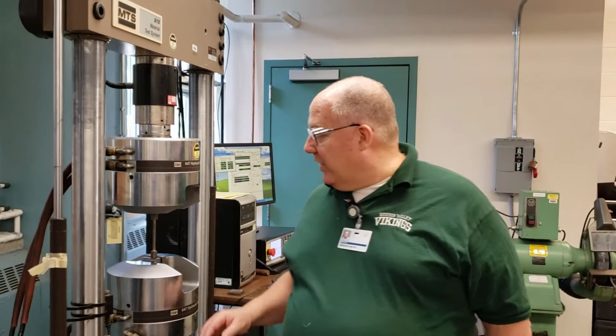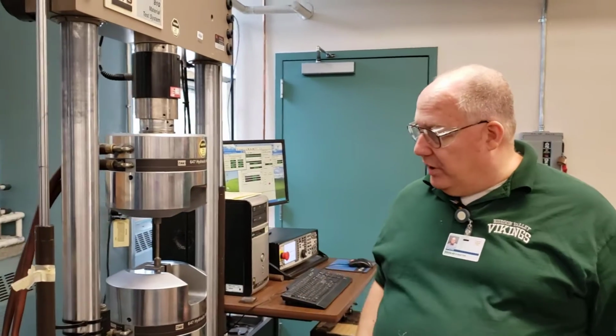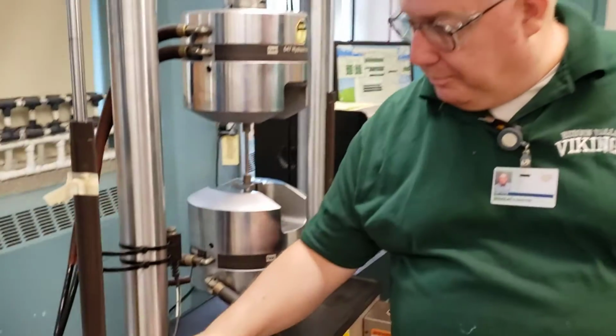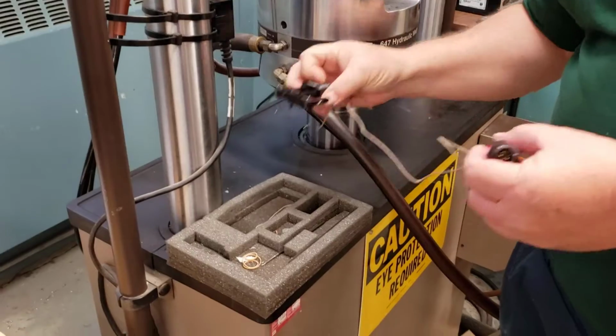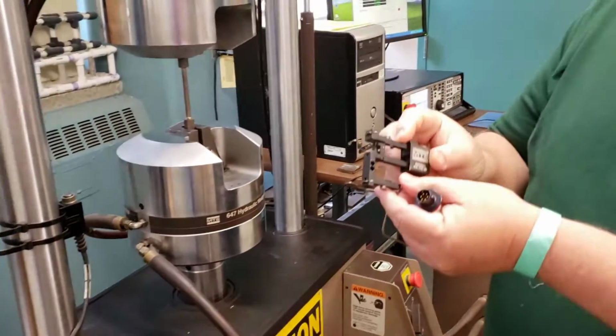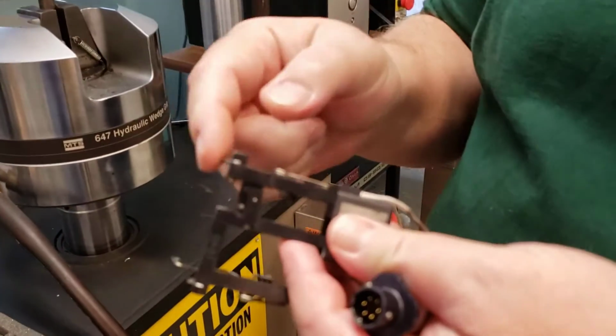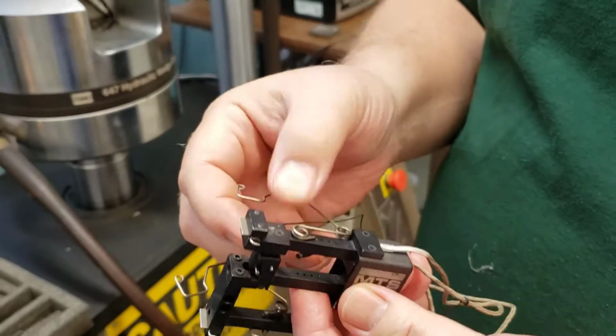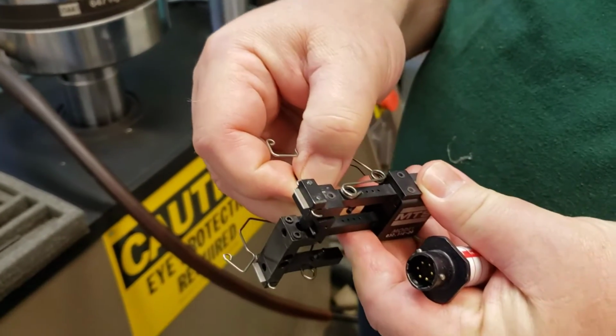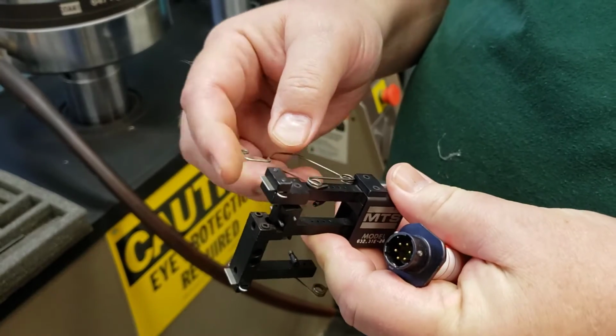Let's talk a little bit about setting up the extensometer on this machine. It's a little more work. The extensometer is a breakaway extensometer. It's right here, and you'll see that this arm moves up and down. There's a locking pin that can come out of it. I don't want to take it out yet. I'll do it when I mount.